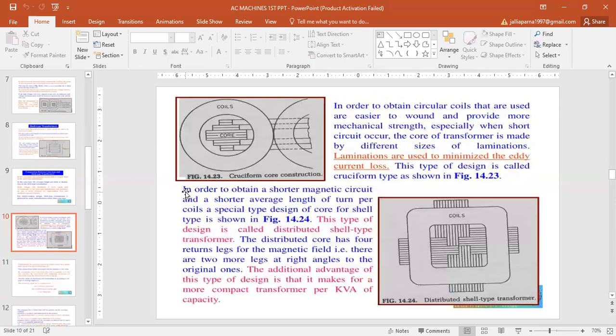Next one is, in order to obtain circular coils that are easier to wound and provide more mechanical strength, especially when short circuits occur, the core of the transformer is made by different sizes of laminations. Laminations are used to minimize the eddy current losses. This type of design is called cruciform type. In order to obtain a shorter magnetic circuit and shorter average length of turn per coil, a special type of design of core for shell type is used. This type of design is called distributed shell type transformer.